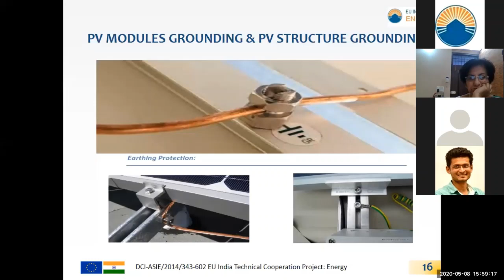Maintenance free earthing. The maintenance free electrode is designed as per the IEC 62561 standards. Some features of maintenance free earth electrodes: it ensures maximum conductivity, it contains a highly conductive compound, it is corrosion free and highly rust resistant, has least variation in ohmic value, and has a large surface area to carry a large fault current.